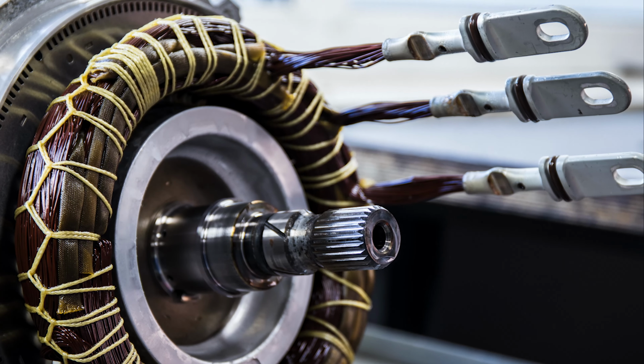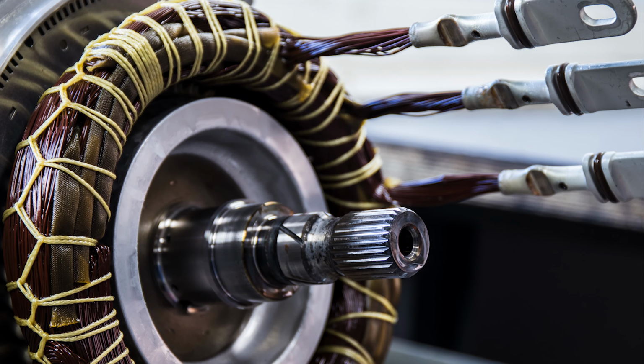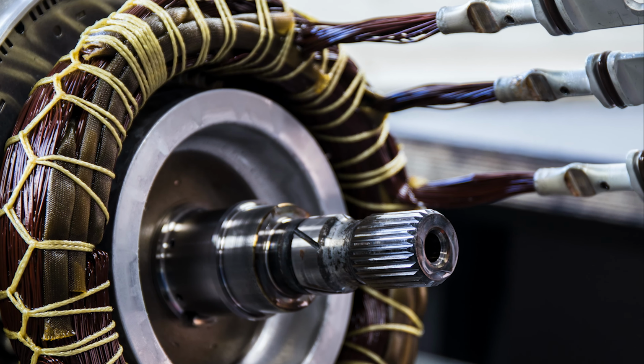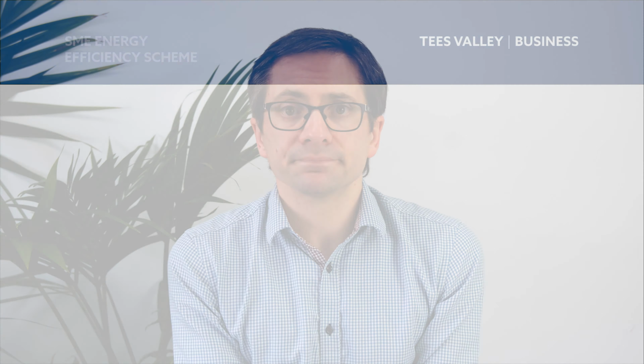Another type of motor, called a permanent magnet AC motor, may be useful where very precise speed or torque control is needed. They use powerful magnets in the rotor rather than the coils found in induction motors. The power in the stator coils is then electronically controlled to ensure it synchronises with the rotation of these magnets. These can be very efficient motors, but their precise engineering and the rare earth metals used for the magnets can make them expensive.